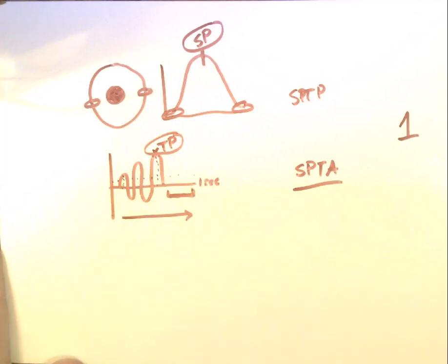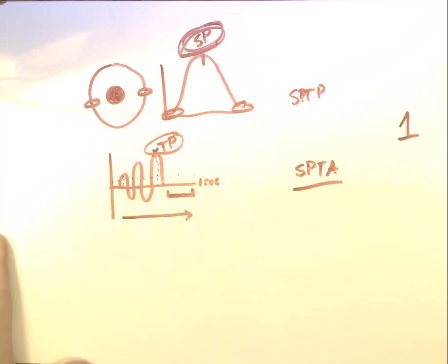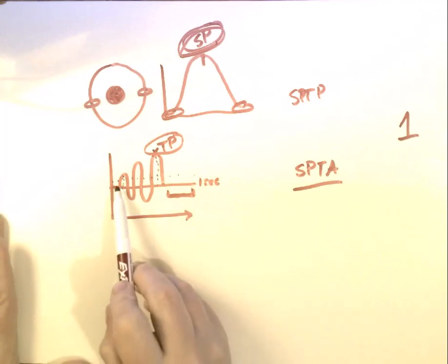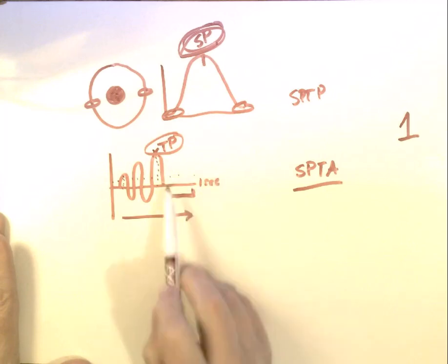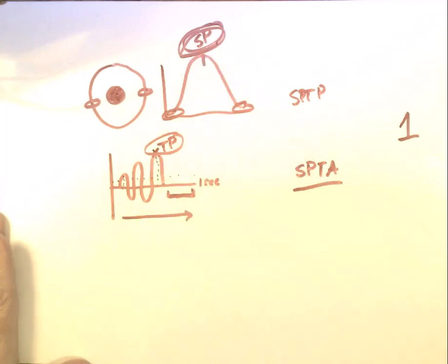This moment in space and this moment in time is just a fraction of the sound energy that the patient is experiencing. So we know that we're always giving them that spatial peak. There's no way to only give them the edge of the sound beam, but we also know that they're always getting a mix of intensities over time. And so what we really are concerned about is what is their average of getting sound energy, not getting sound energy, and what does that look like over the area of the beam.